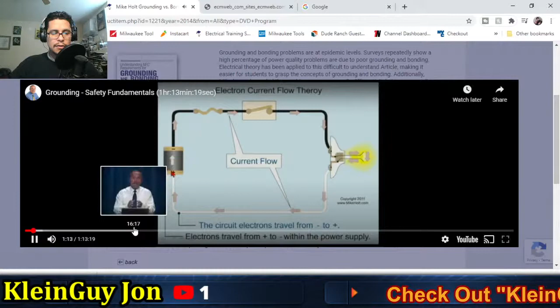Then when you have a fault, a current with a low impedance path is going to cause a high fault current. Now, the way circuit breakers operate, the higher the current, the quicker it takes for that device to open. Have a 120-volt circuit here, and then it's 240 line to line. There's a fault between one phase and the ground. This is a 120-volt ground fault. Current's traveling on this conductive path right here.